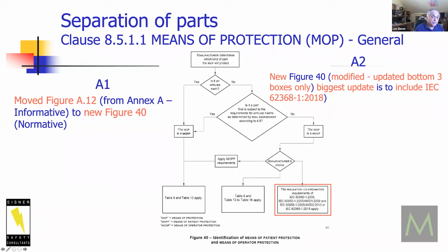The other option is within the 601 standard to use the tables, and all this is for separation of parts, which means creepage and clearance, which is spacings, so separation, and insulation, which means dielectric or hipot testing. So these are means of operator protection within the 601 standard. This is using external standards. Or if you really want, and these are all manufacturer's choice, I think is the words, you could use means of patient protection, which is also within 601 standards. So these are different tables.